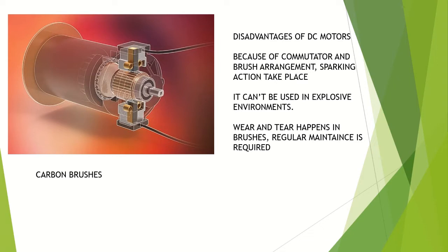And here comes the disadvantage. With this brush arrangement and commutator arrangement, some friction happens between the brushes and the commutator. Because of this friction, wear and tear happens. So daily some maintenance is required for the DC motor, and at the commutator some sparking also happens. Because of this sparking, it cannot be used in explosive environments.